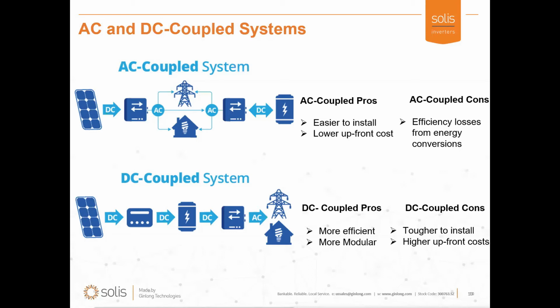It can then go to a separate battery system through a converter that changes it back into DC. The energy storage device in this case will typically have its own inverter that allows the battery to change its DC energy back into AC to feed the loads independently of the PV inverter. Tesla, Sonnen, and Generac sell AC coupled systems.